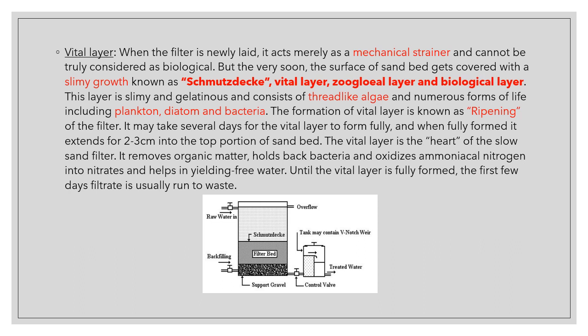Schmutzdecke is just German for dirty skin, so you can remember it like that. This layer is slimy and gelatinous, and it consists of thread-like algae and numerous forms of life, including plankton, diatoms, and bacteria. The formation of this vital layer is known as ripening of the filter. It doesn't occur just suddenly as soon as we put the sand in. It actually takes several days for the vital layer to form fully.